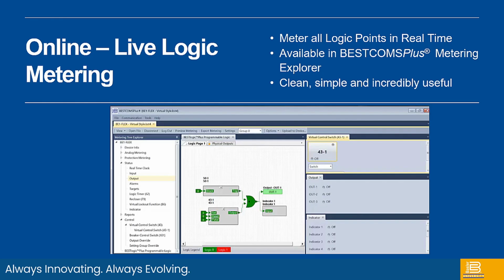So again, this is live status. This is exactly what's going on inside the box, and very helpful if you have complex logic, or if you're stuck in commissioning, or if you have a troubleshooting situation where something's not doing what you want it to do. Let's say if you have counters or feedback loops or all sorts of other fun, non-direct things, they could be seen in direct status by using that live logic metering.